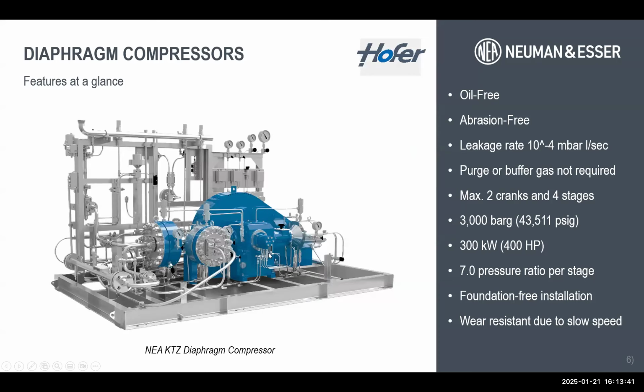Just a little more information about the diaphragm compressor. This is the application that you see in the mobility market, for example. We talked a lot about the mobility market here in the meetings with Brian and the colleagues. They can handle very high pressures very well, but they are somewhat limited in flow. On a single machine from 30 bar to 500, you can roughly get 60 to 70 kilograms per hour on a diaphragm compressor. If you're talking about higher flows, then you need more units. And that's where their limitation is.